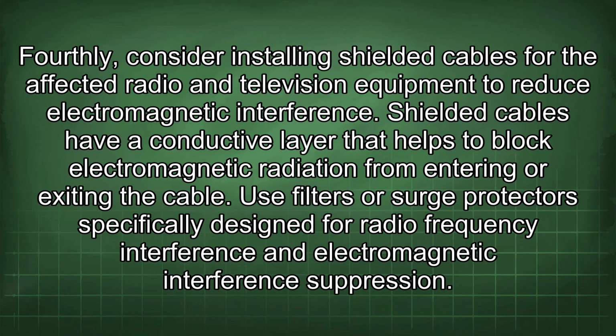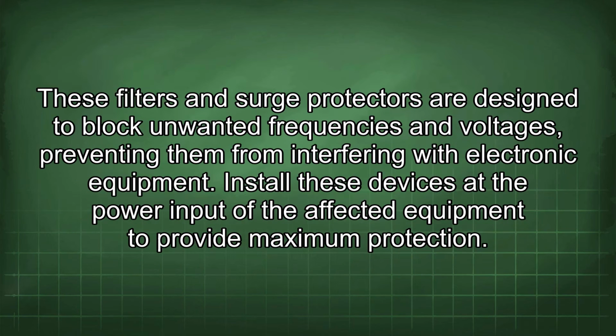Fourthly, consider installing shielded cables for the affected radio and television equipment to reduce electromagnetic interference. Shielded cables have a conductive layer that helps to block electromagnetic radiation from entering or exiting the cable. Use filters or surge protectors specifically designed for radio frequency interference and electromagnetic interference suppression. These filters and surge protectors are designed to block unwanted frequencies and voltages, preventing them from interfering with electronic equipment. Install these devices at the power input of the affected equipment to provide maximum protection.